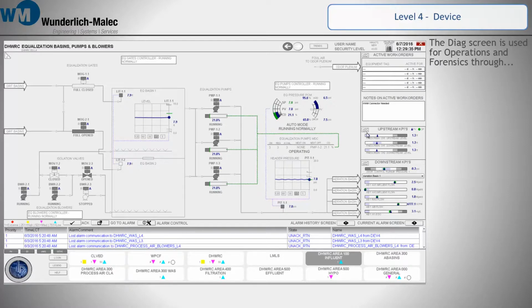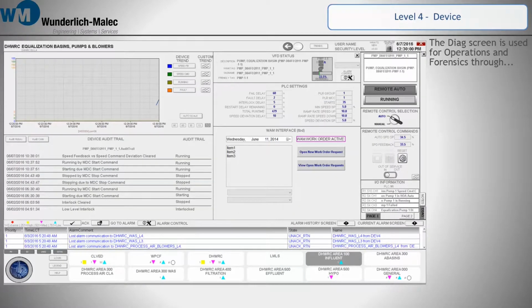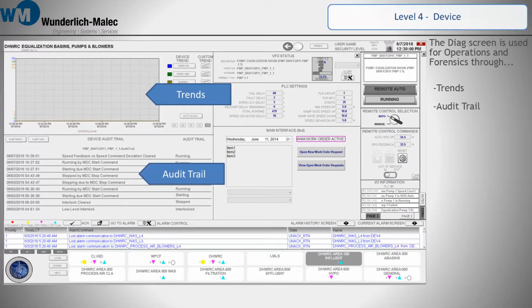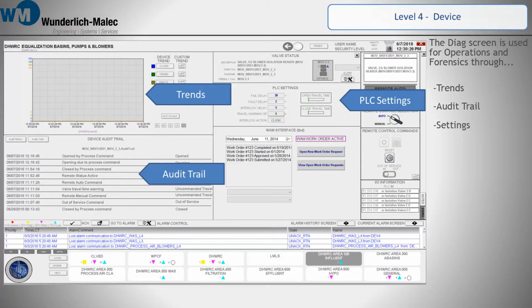When we select a piece of equipment, the Diagnostic tab on the right can be used for operations and forensics. There's device-specific trending. The Audit Trail lists the last 10 changes the equipment has made, but can be expanded to the last 30 days to look for trends or failures. The PLC Settings gives a more in-depth look at what is expected from the equipment. For example, the pump shows restart delay remaining and how many starts, while the valve will give the interlock action and show the open-close travel times. The equipment work order shows current work that needs to be done on the equipment, as well as repairs that have been made and completed in the past.